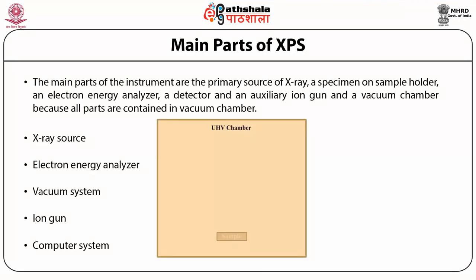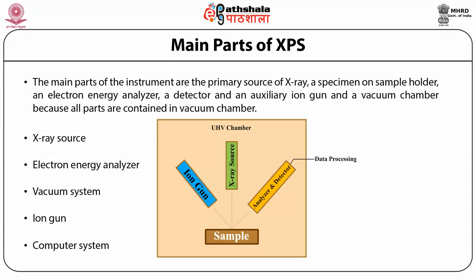To understand X-ray photoelectron spectroscopy clearly, we need to know about the instrumental part of the XPS technique. The main parts of the instrument are the primary source of X-rays, a specimen, a sample holder, an electron energy analyzer, a detector, an auxiliary ion gun, and a vacuum chamber. All these parts are contained in the vacuum chamber. The figure shows the general arrangement of an X-ray photoelectron spectroscopy instrument.